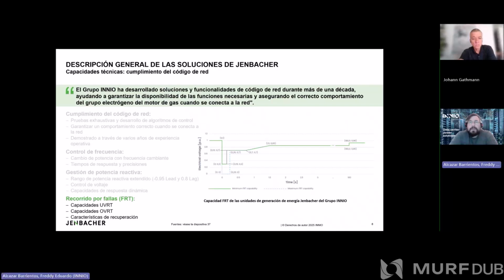Network codes have evolved, and today it is a requirement that all units, regardless of their technology, can withstand or remain connected during a voltage dip. This example I'm showing you here is what is called LVRT, low voltage ride through. Our units can withstand drops of 30% to 0% for up to 250 milliseconds, which is normally the maximum time that is set by grid codes.